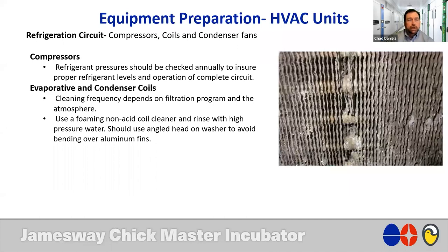All too often I've visited hatcheries that have ventilation equipment that's only a few years old, and you'll see a coil that has been damaged by an acid type cleaner. Wasn't rinsed thoroughly, and unfortunately that greatly reduces the efficiency of that coil. So you lose a lot of your cooling capacity just because you didn't use the right cleaning solution for that. After cleaning, a fin comb should be used to just make sure that all of the fins are good and straight.